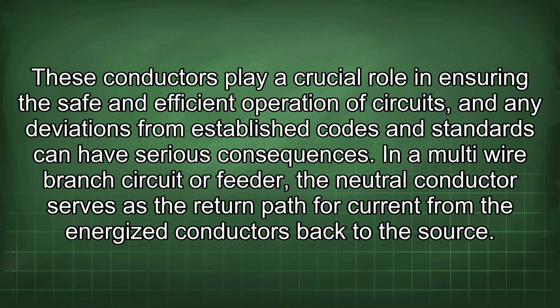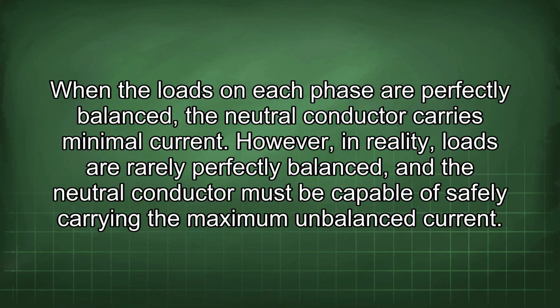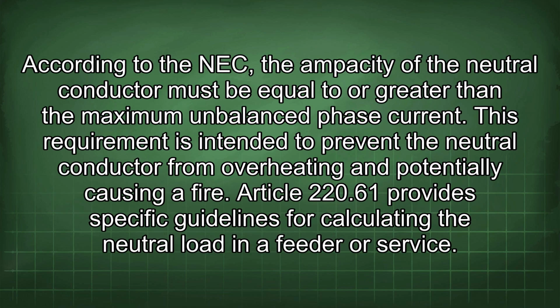In a multi-wire branch circuit or feeder, the neutral conductor serves as the return path for current from the energized conductors back to the source. When the loads on each phase are perfectly balanced, the neutral conductor carries minimal current. However, in reality, loads are rarely perfectly balanced, and the neutral conductor must be capable of safely carrying the maximum unbalanced current. According to the NEC, the ampacity of the neutral conductor must be equal to or greater than the maximum unbalanced phase current. This requirement is intended to prevent the neutral conductor from overheating and potentially causing a fire.